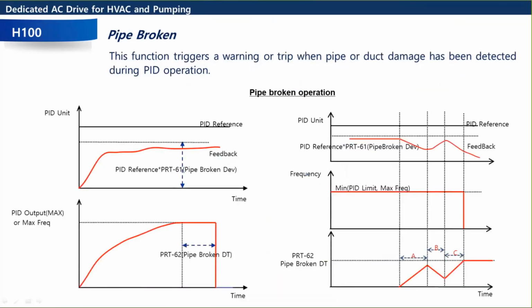Then we have a broken pipe detection. This is similar to the underload detection, similar but different. You could have a trip or a warning happen whenever we have a low pressure and a high speed. If we are running a PID loop, some of you hopefully watched our PID webinar, last week or maybe two weeks ago. If not, it's on our YouTube page, you can check it out. When you enable PID, that's what all these functions are related to. So that's your pressure loop.